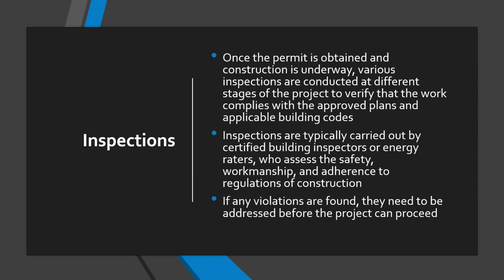During the final inspections, after all penetrations to the outside have been sealed, a blower door test is performed, which verifies by air testing the air barrier that was previously visually verified during the first inspection. This test does not find or locate the leakage. Instead, it only measures the total leakage to verify it's at or below acceptable levels based on the conditioned volume.